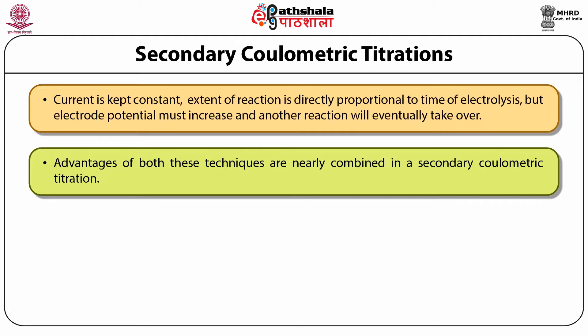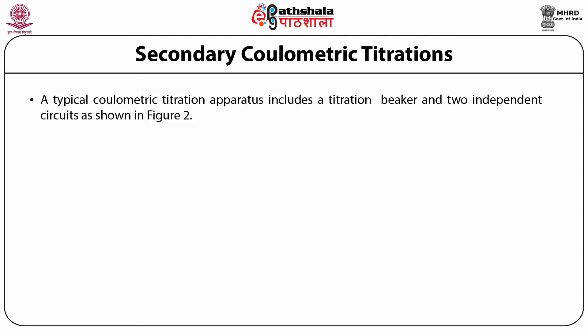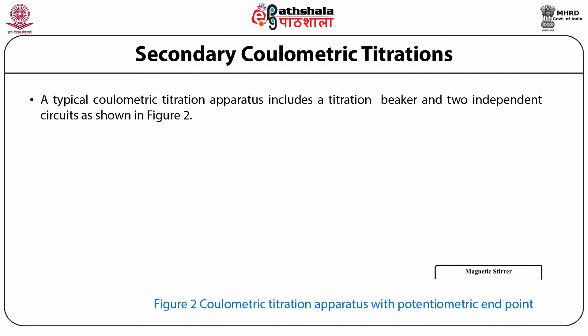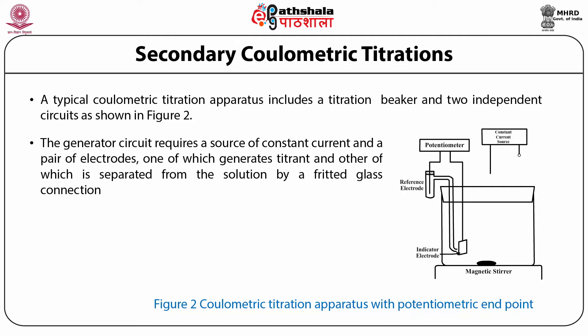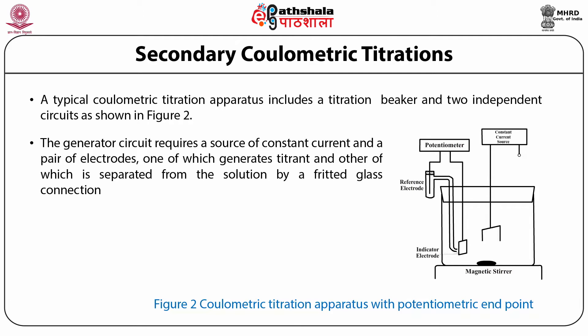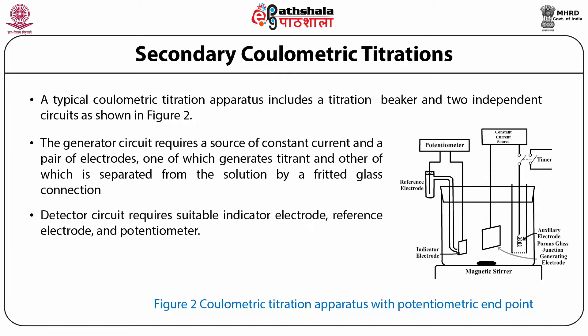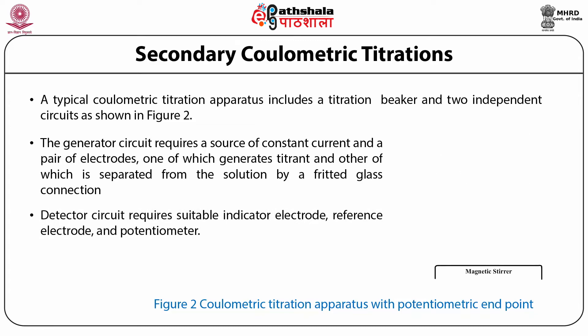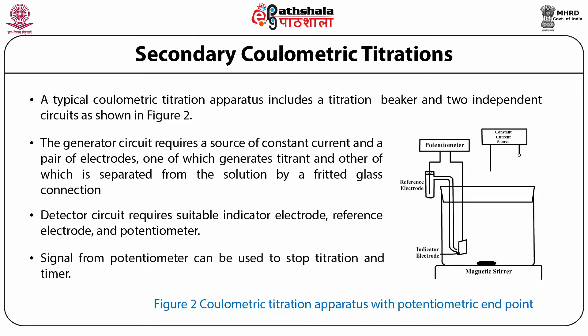In coulometric titration, the substance to be determined is indirectly titrated with a reagent that is electrolytically generated in situ. A typical coulometric titration apparatus includes a titration beaker and two independent circuits as shown in figure 2. The generator circuit requires a source of constant current and a pair of electrodes, one of which generates the titrant and the other of which is separated from the solution by a fritted glass connection. For precision and convenience, the switch controlling the current source also controls the timer. The detector circuit requires a suitable indicator electrode, reference electrode, and potentiometer. The signal from the potentiometer can be used to stop the titration and the timer.